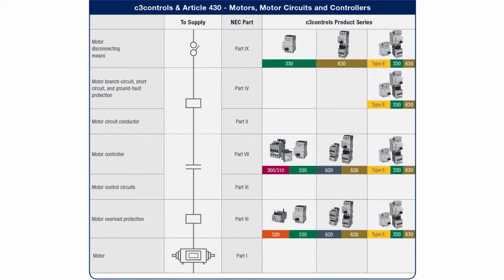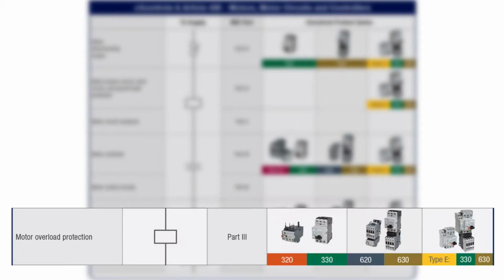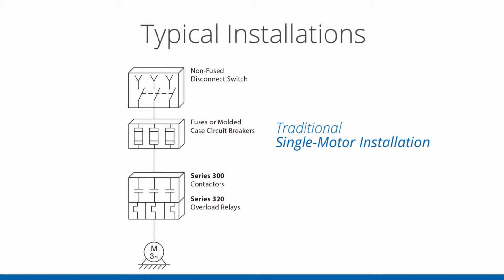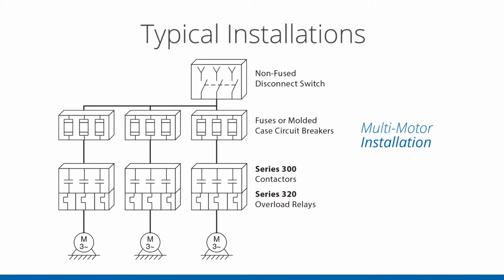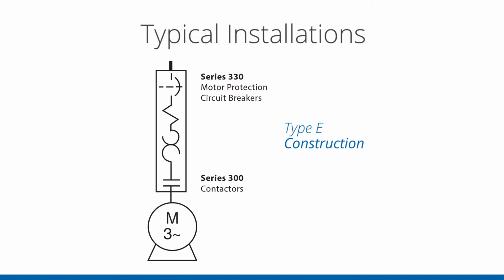Let's take a brief look at the National Electric Code Article 430 requirements for a motor circuit. Relative to utilizing a combination motor controller, specifically Type E or Type F, we will focus on 4 elements: motor disconnecting means, motor branch circuit, short circuit, and ground fault protection, motor controller, and motor overload protection. So we'll first talk about the typical type of motor installations and solutions people may use within the National Electric Code for meeting these requirements. There are 4 examples: traditional motor installation, multi-motor installation, group installation, and Type E construction.